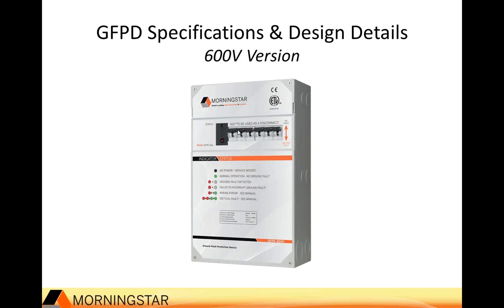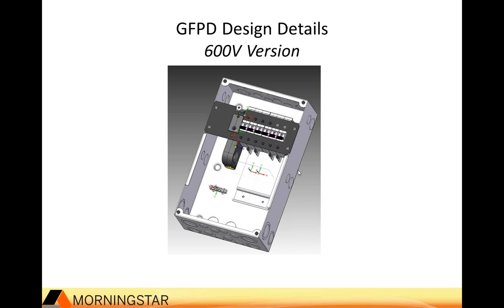In this case, you can see here we have ganged breakers to fully isolate both the negative and the positive of the array. Okay, so obviously this is a lot larger because we have to deal with 600 volt tolerances, but the functionality is the same. Here's an example of the inside of the package, just to give you an engineering drawing here. So here's the wire aperture itself, so the wiring is going through here, and then we have both the positive and negative legs.